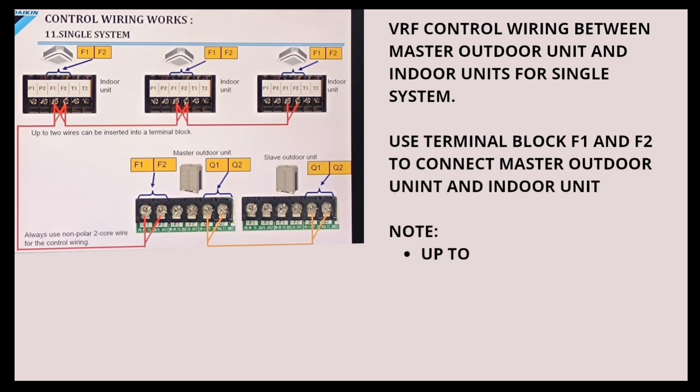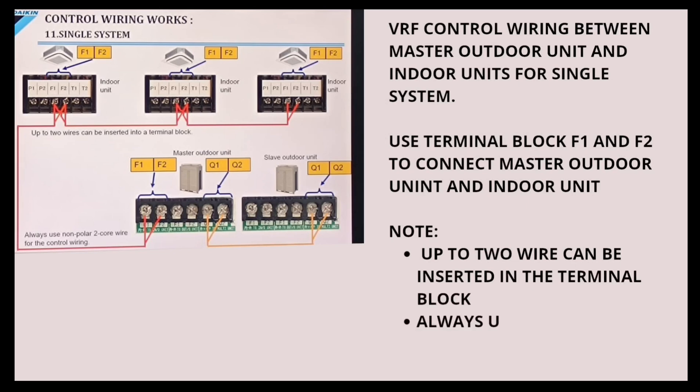VRF control wiring between Master Outdoor Units and Indoor Units for a single system. Use Terminal Block F1 and F2 to connect Master Outdoor Units and Indoor Units. Note: up to two wires can be inserted in the terminal block. Always use non-polar two-core wire for the control wiring.